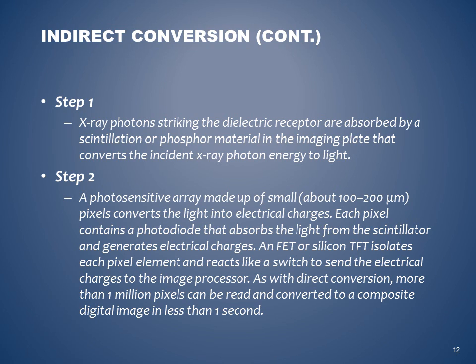Each pixel contains a photodiode that absorbs the light from the scintillator and generates electrical charges. An FET, or silicon TFT, isolates each pixel element and reacts like a switch to send the electrical charges to the image processor. As with direct conversion, more than 1 million pixels can be read and converted to a composite digital image in less than 1 second.